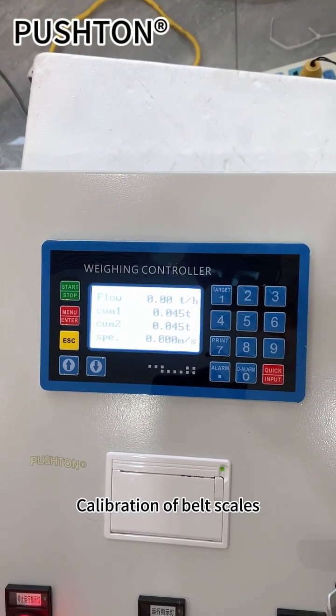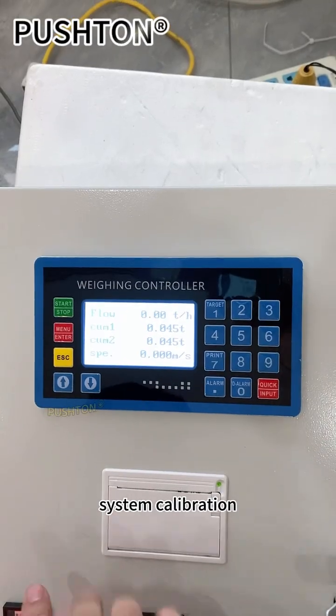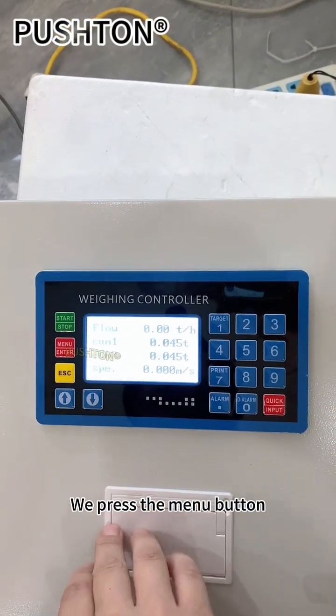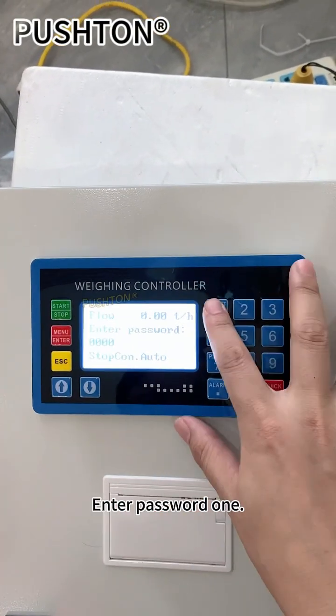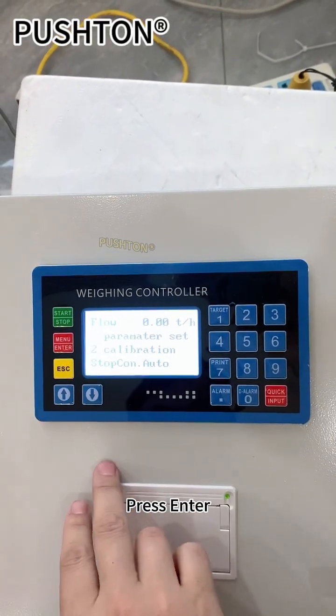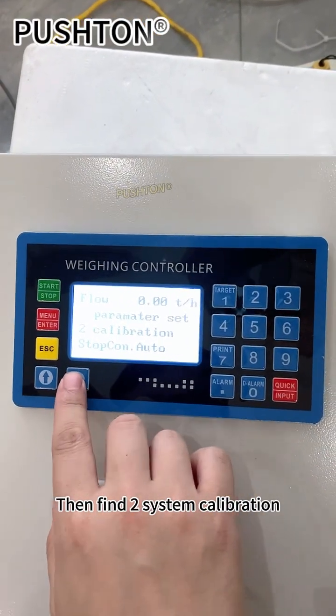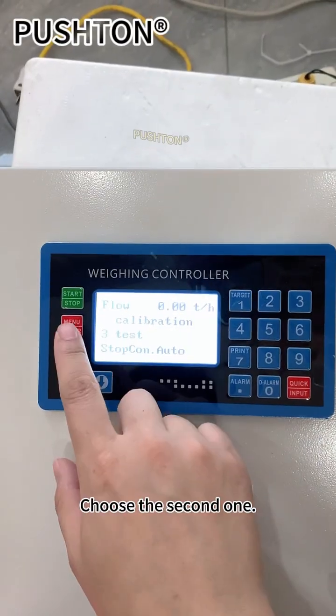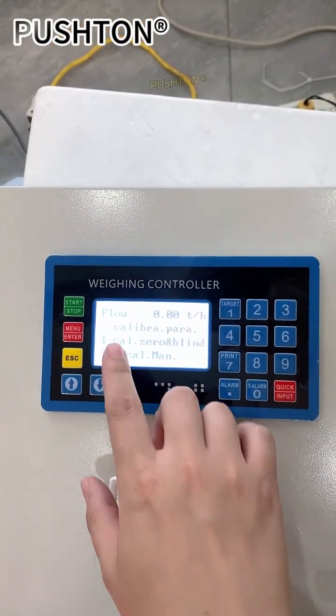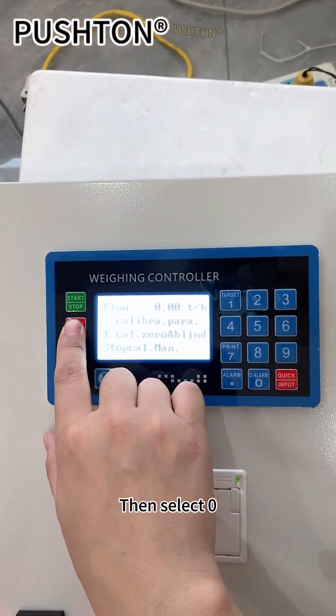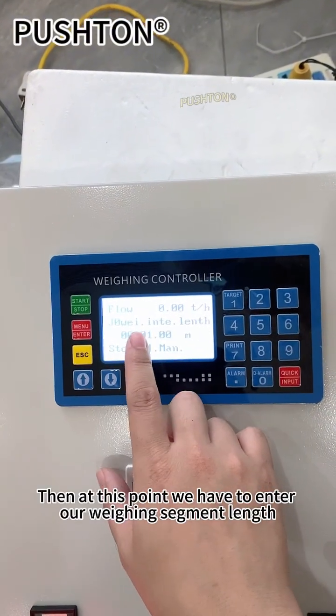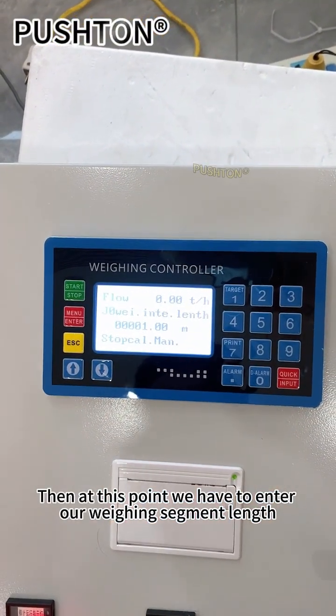Calibration of belt scales. Step 1. System calibration. We press the menu button. Enter password 1. Press enter. Then find system calibration. Choose the second one. Then press enter. Then select 0. At this point we have to enter our weighing section length.